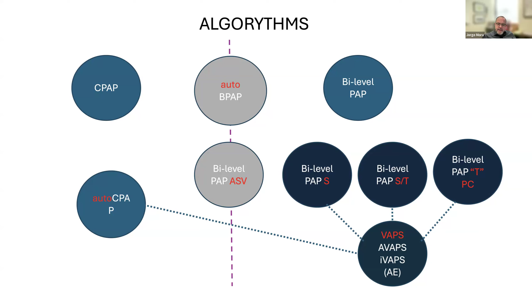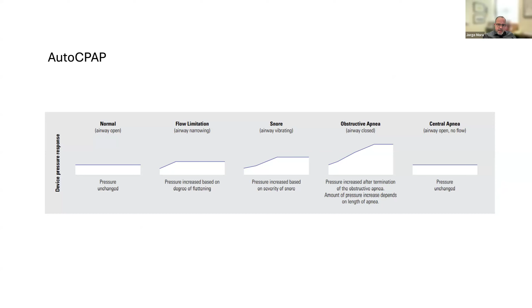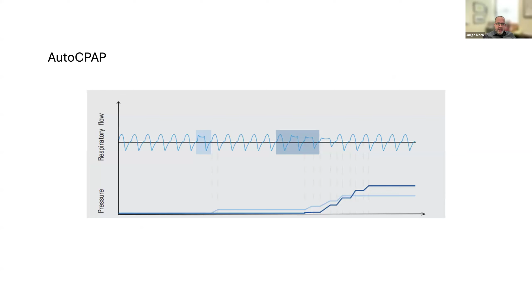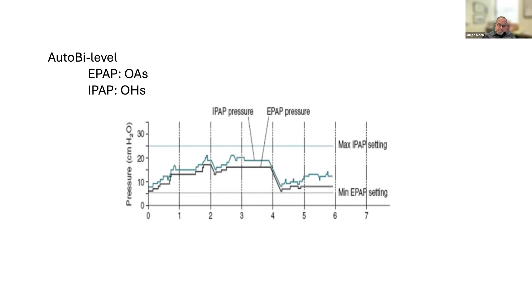That being said, auto CPAP is a simpler mode, and I'm not going to go into much detail on this. It's able to assess flow limitation, snoring, and vibration, and based on this, will self-adjust the EPAP pressure within a predefined range. In auto bilevel, depending on which brand you're using, and since Philips is out of the equation in many cases, we usually now have a fixed pressure support. Auto bilevel PAP is used, again, as a mode to treat sleep apnea and also as a ventilation mode, which is true and false, as we will see. But the problem is there is no sensing of volume. There is no targeting here. The difference between the IPAP and the EPAP will be the same during the whole respiratory cycle, and the pressure is adjusted by an algorithm based on flow obstruction and flow limitation.